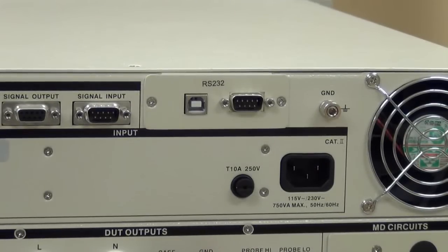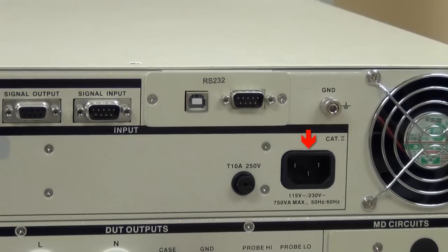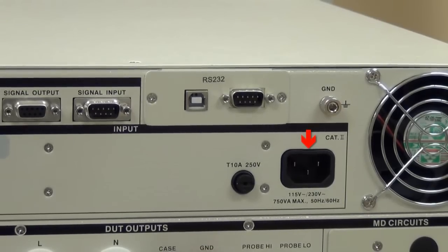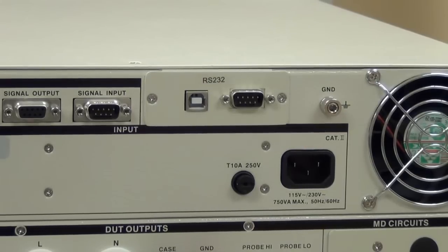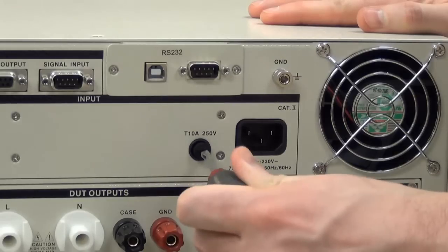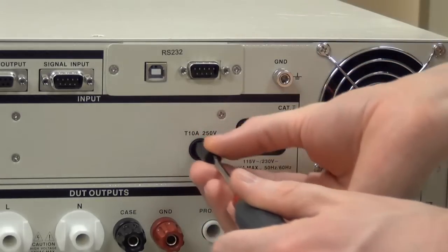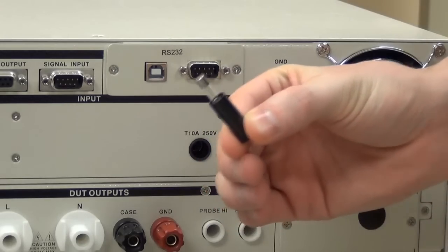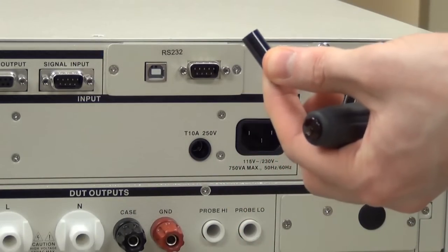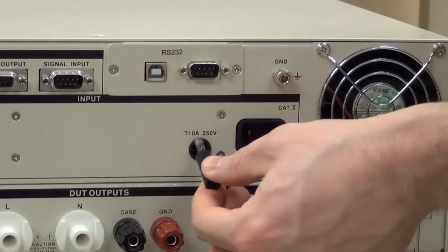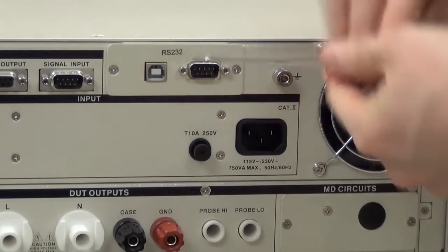The input power receptacle is a standard IEC 320 connector for connection to a standard NEMA style line power cord. The fuse receptacle is used to change the fuse. To change the fuse, unplug the mains cord and turn the fuse receptacle counterclockwise. The fuse compartment will be exposed. Please replace the fuse with one of the proper rating. The fuse that comes standard with the Omnia II instrument is a 10 amp slow blow 250 volts AC fuse.